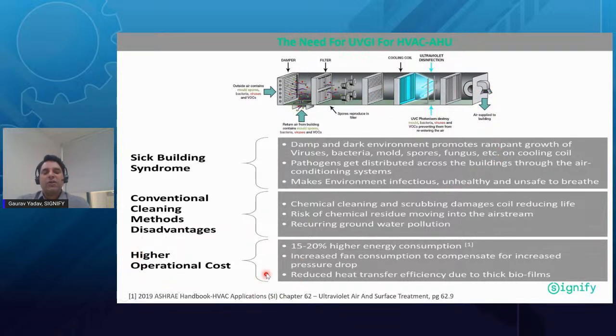Third is the higher operational cost. When the biofilm gets added onto the cooling coil, your HVAC system needs to work harder. Your fan needs to work harder to maintain the same temperature in the indoor environment. So that is why the efficiency of the overall system is also a challenge, and you want to reduce the operational cost. That is why a UVGI system should also be in place.